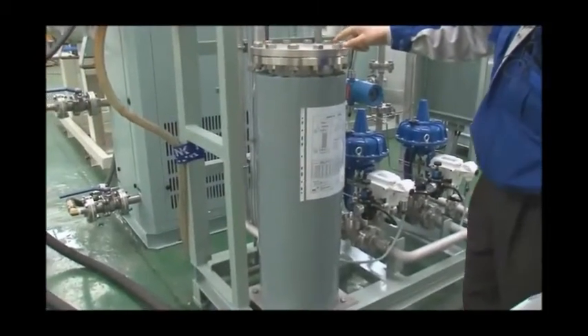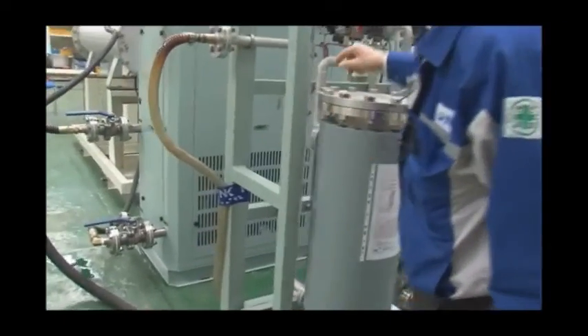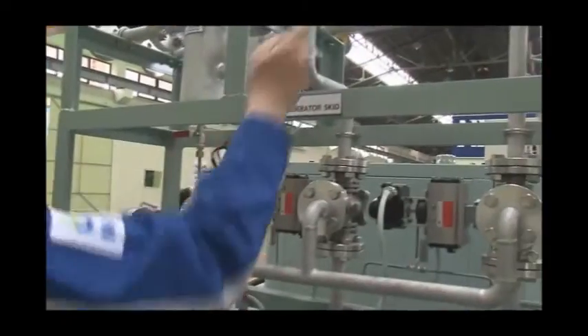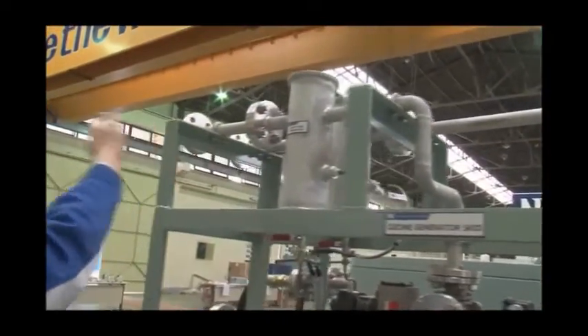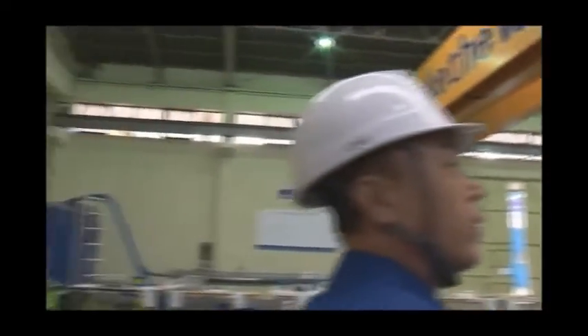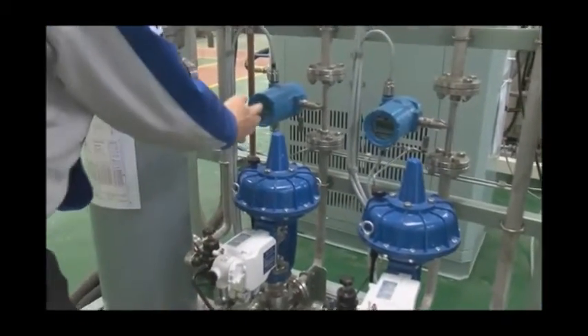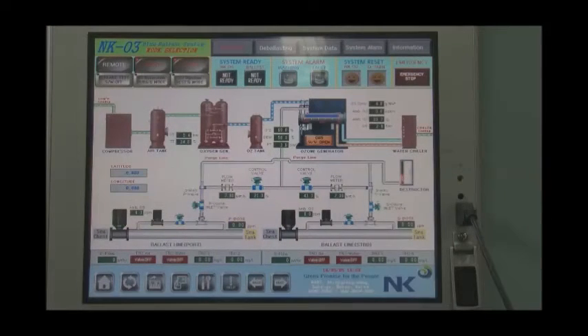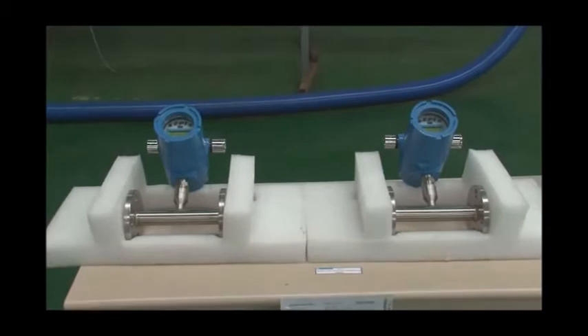The produced ozone flows to the ozone destructor at the initial stage. And when the ballast pump is started, ozone flows direct to the ozone injection unit at discharge side of ballast pump. This actuation is achieved through flow control valve, flow meter, three-way valve in this flow control module. The ozone production capacity and flow control is automatically adjusted proportionally according to the ballast flow volume measured by seawater flow meter.